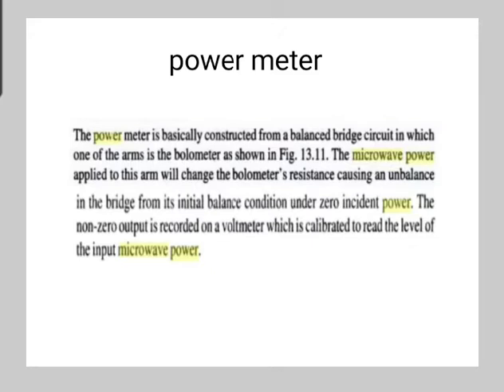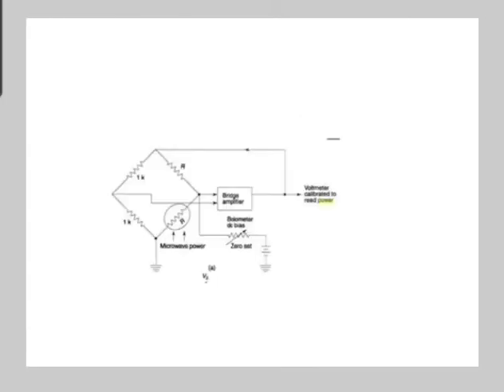The power meter is basically constructed from a balanced bridge circuit in which one of the arms is a bolometer. The microwave power applied to this arm will change the bolometer's resistance, causing an unbalance in the bridge from its initial balance condition under zero incident power, and the non-zero output is recorded on a voltmeter, which is calibrated to read the level of the input microwave power. So, power meter: here is a diagram which shows the image of a microwave power meter. It is a circuit diagram.